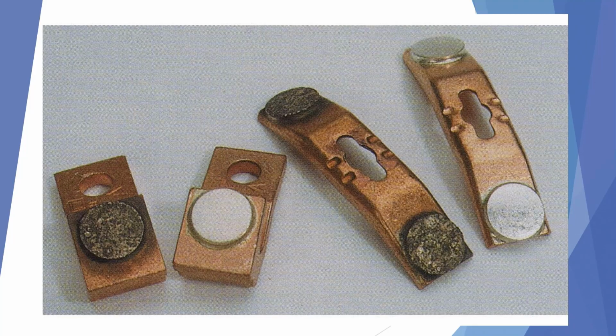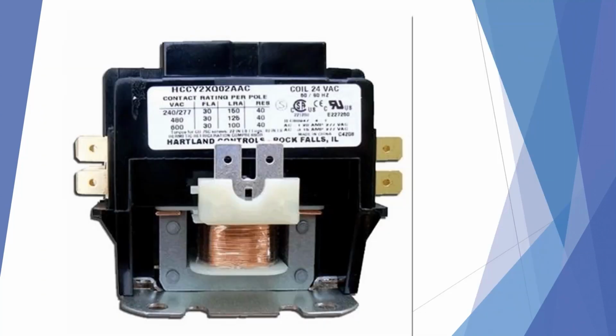Over time and use, the contacts will become pitted and will provide an uneven contact which can affect the operation of the load. Contactors should be checked during periodic maintenance to make sure the contacts are still in good shape. You also want to make sure that you do not exceed the voltage and amp draw rating listed on the contactor. Excessive voltage and amp draw can lead to early failure of the contactor.